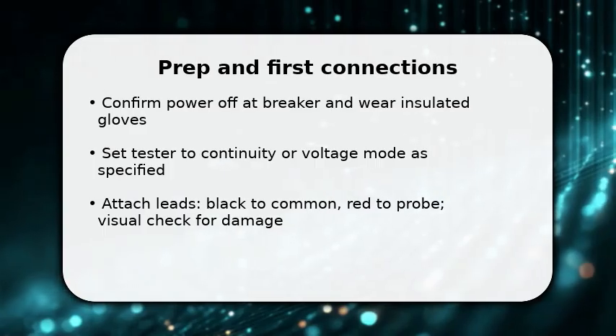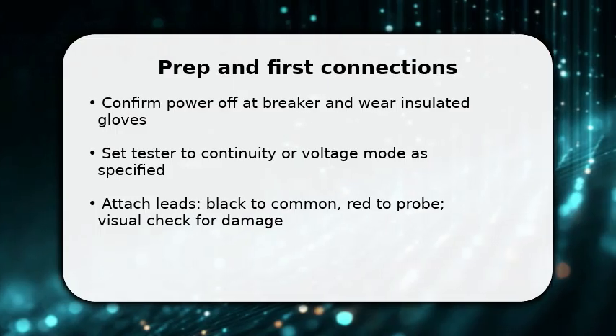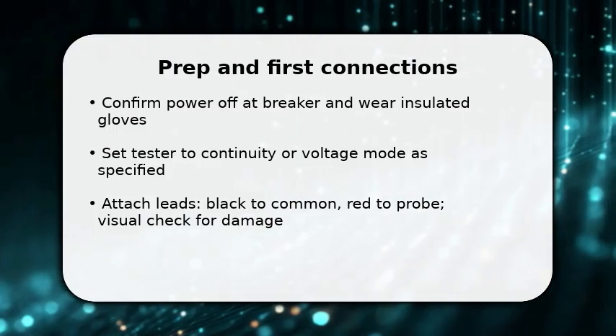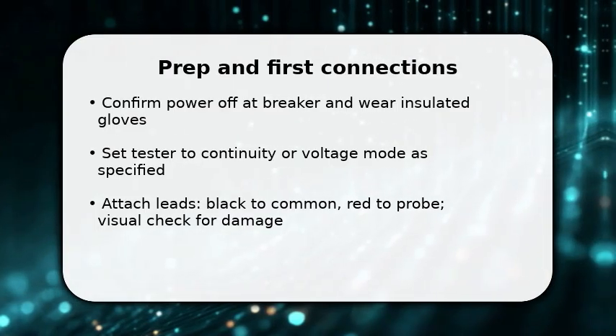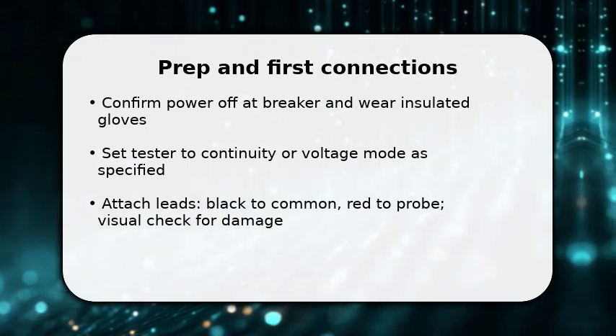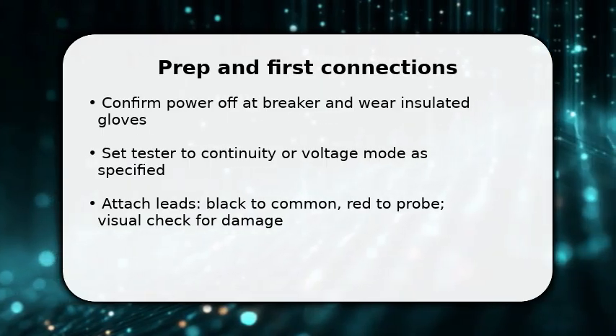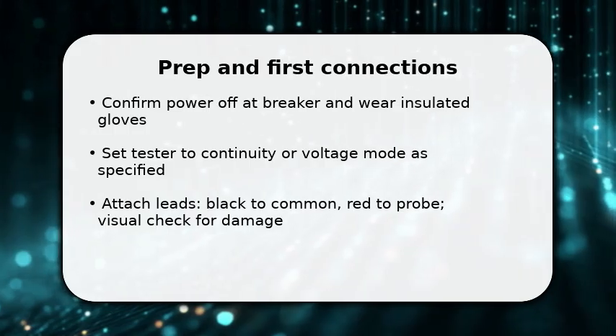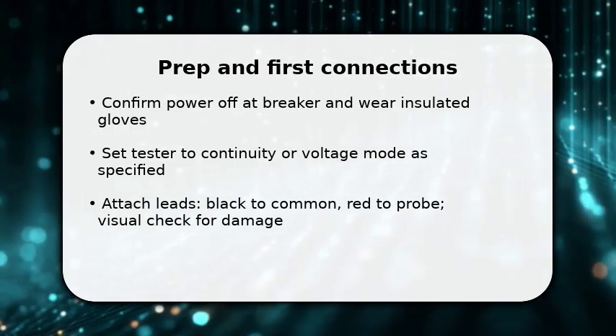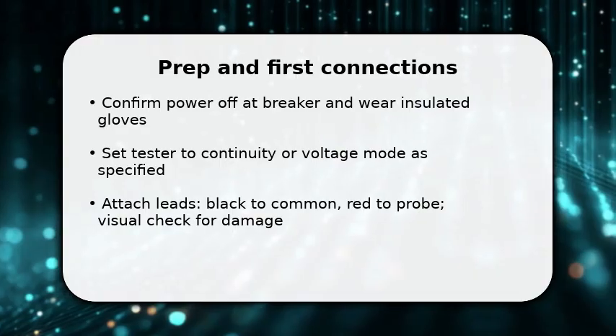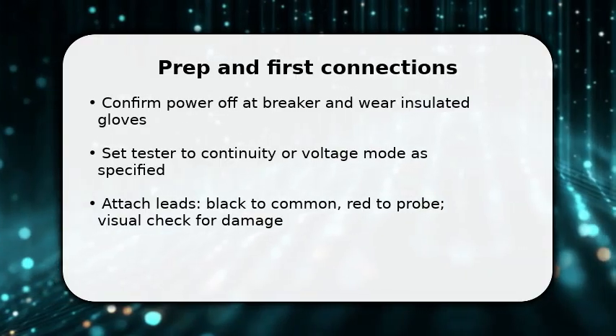You start by confirming the circuit is safe and the tester is configured. Turn off the breaker, but leave the device accessible. This prevents surprises. Once done, select continuity or voltage mode on the circuit alert tester and inspect leads for cuts or corrosion. Make sure the black lead is on common and the red is the probe.